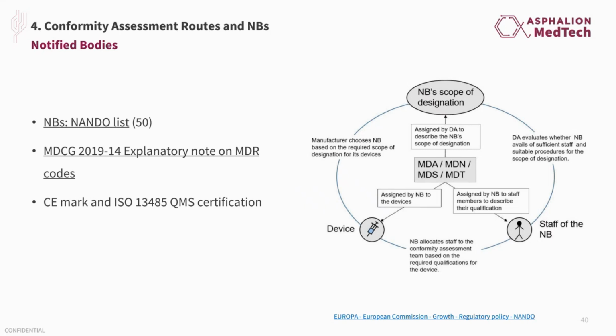Not all notified bodies are able to assess and give conformity for all types of devices. For this reason, there are MDR codes, which are codes associated with medical devices. The notified bodies are designated by the European Commission to give conformity to a specific MDR code. So it is necessary to search the NANDO list for the codes applicable to your device. Among those, then select your notified body between those that can certify your product, right?